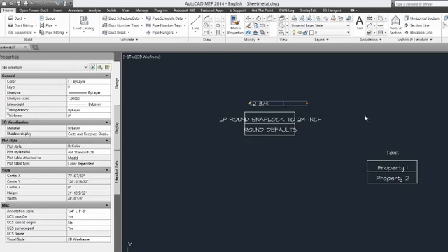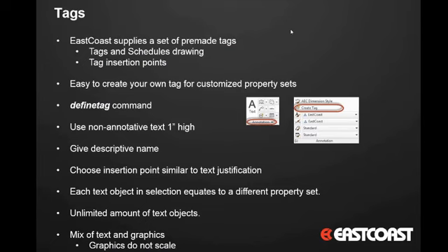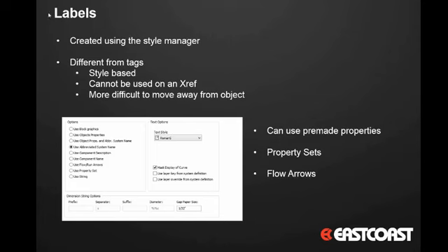Going back to the slide, we've covered everything on the tags section. Now let's get into labels. Labels are a little different from tags — tags are created using text and multi-view blocks with the define tag command, whereas a label is created using the Style Manager. Labels are style-based, and importantly you cannot use a label through an xref. With tags, you can certainly xref a duct drawing into your current drawing and tag all that duct in the xref. Labels are unable to do that.